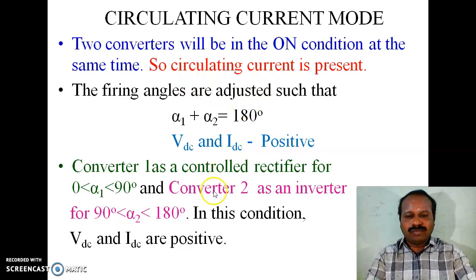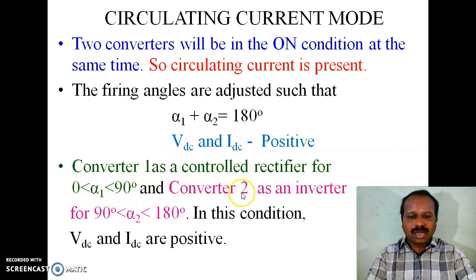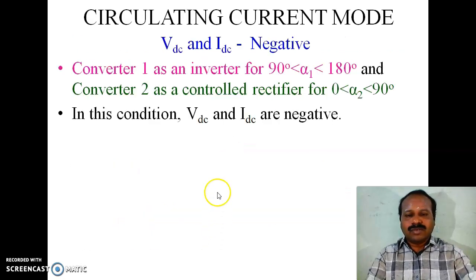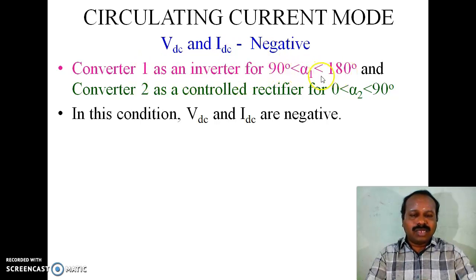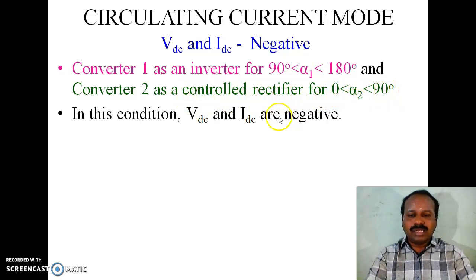For positive values of VDC and IDC, Converter 1 acts as a controlled rectifier for 0 < alpha 1 < 90° and Converter 2 acts as an inverter for 90° < alpha 2 < 180°; in this condition both VDC and IDC are positive. For VDC and IDC negative, Converter 1 works as an inverter for alpha 1 > 90° and Converter 2 acts as a controlled rectifier for 0 < alpha 2 < 90°; in this condition both VDC and IDC are negative.